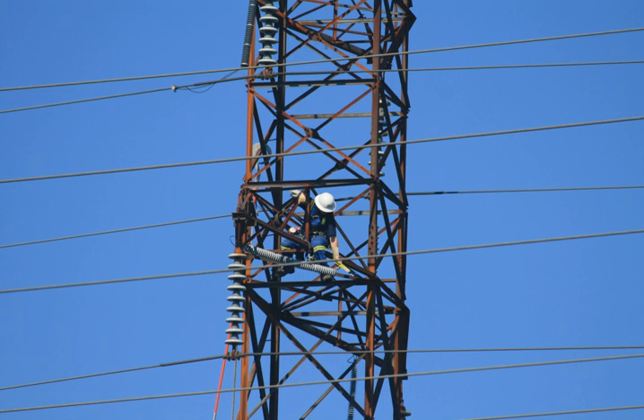A lightning arrestor may be a spark gap or may have a block of a semiconducting material such as silicon carbide or zinc oxide. Thyrite was once a trade name for the silicon carbide used in arrestors. Some spark gaps are open to the air, but most modern varieties are filled with a precision gas mixture, and have a small amount of radioactive material to encourage the gas to ionize when the voltage across the gap reaches a specified level. Other designs of lightning arrestors use a glow discharge tube, essentially like a neon glow lamp, connected between the protected conductor and ground, or voltage-activated solid-state switches called varistors or MOVs.